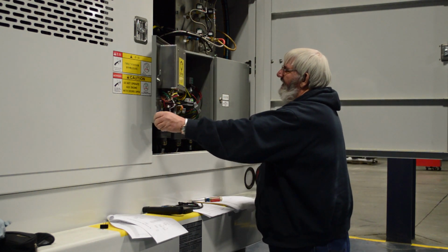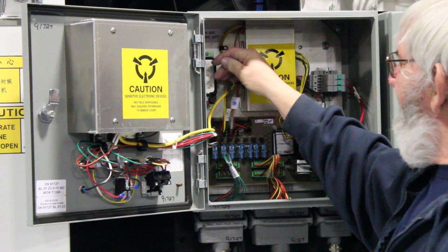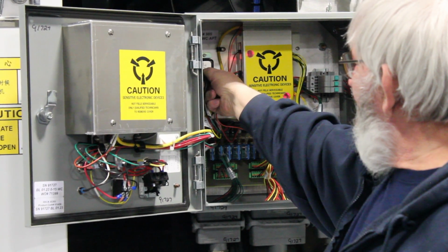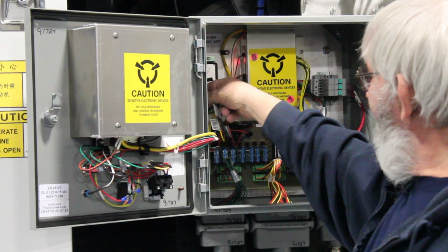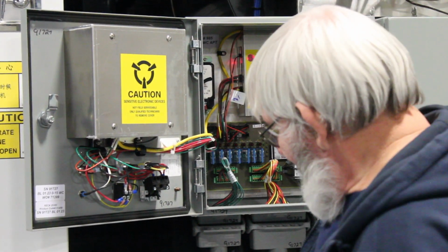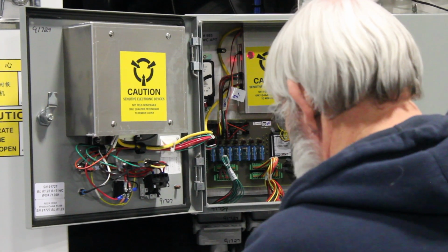In this particular case, we're going to go to the air pressure transducer, which is located inside your heater box. You have your low pressure and your high pressure. We will remove the line off of the high pressure. We would connect our manometer up to our air pressure transducer.